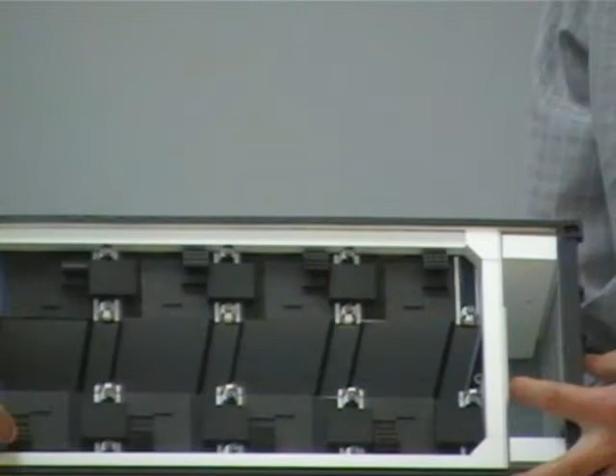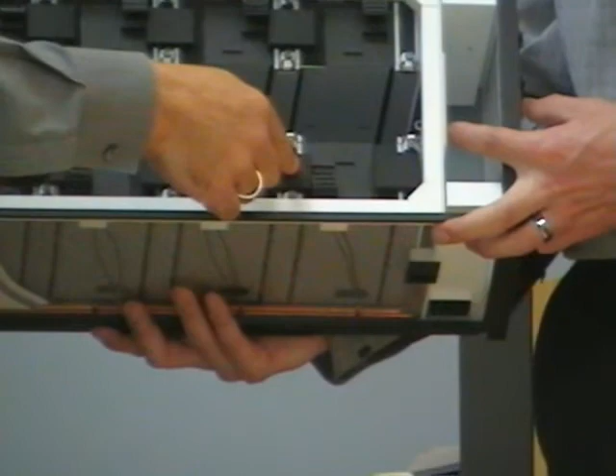It's like 200 kilowatts - take 200 of your air dryers, turn them on, put them in a room, and run away. So the trick is, as the air exits each rack and before it goes into the next one, there's a heat exchanger that takes the hot air that's exited, cools it down, and makes it suitable again.